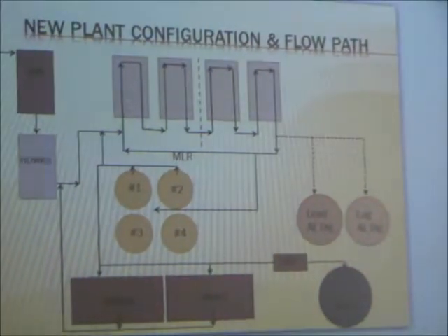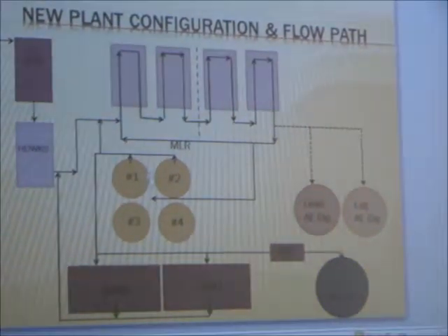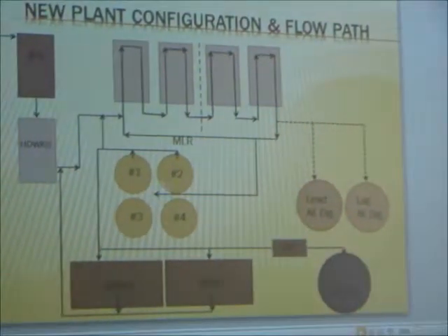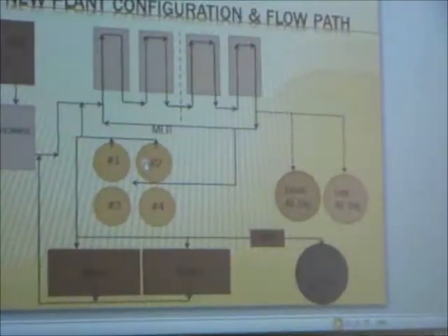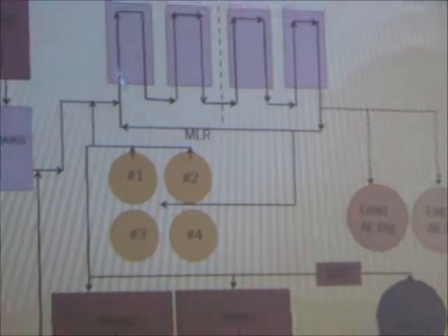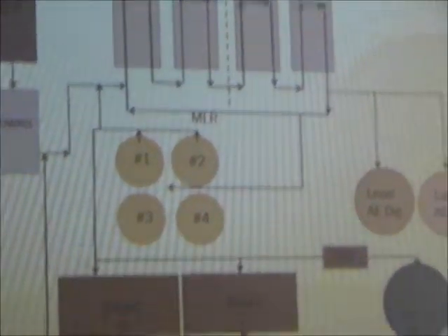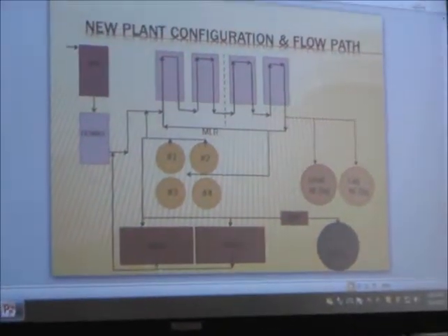So that's your mixed liquor return. A portion of your mixed liquor is going to come into your clarifiers. You're going to get your solids-liquid separation there. On the sludge side of that, so the underflow, your RAS, your return activated sludge, goes into the front end to consume the BOD coming in, and then a portion of that is getting pumped up into these interchange bioreactors, spending a residence time in there.